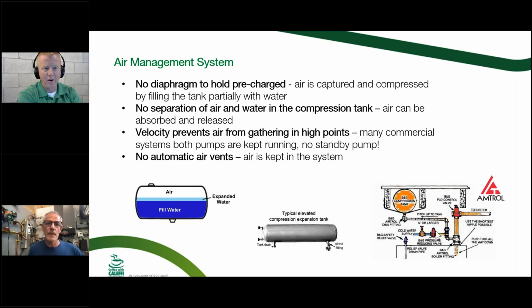Bob, you mentioned it earlier about air elimination. You put an air separator or an air elimination device in your system, and that's a great way to get rid of that air bubble that's going to be in that compression tank, waterlog it, and then start popping pressure reliefs. It's definitely something you need to be aware of. And I would say, similar to this boiler fitting that you talked about before, air scoops are probably better suited towards air management, as opposed to putting an air vent on top of an air scoop. Having a pipe that goes up to this compression tank is going to be the best way to manage the air, keep that air bubble in there, and prevent it from waterlogging.